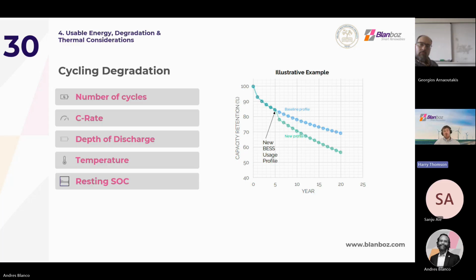Depth of discharge. Operating across the full range of the battery, from 0 to 100% of state of charge, often puts more stress on the battery by using the entire window. A more conservative approach, and a way to reduce the degradation rate, is to avoid the extreme ranges and discharge between 20 to 80% of the battery where appropriate and in line with the operating strategy.